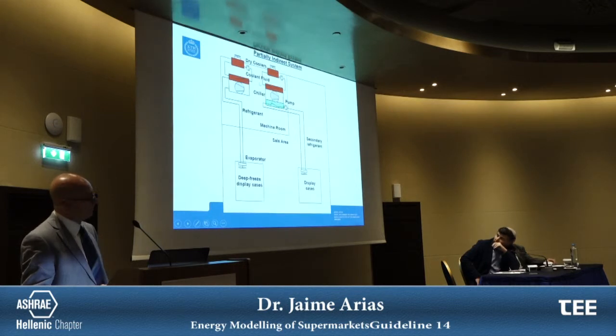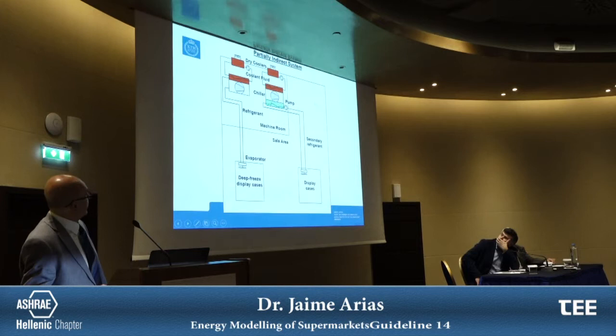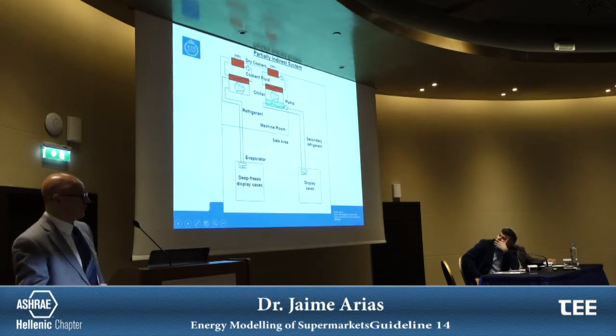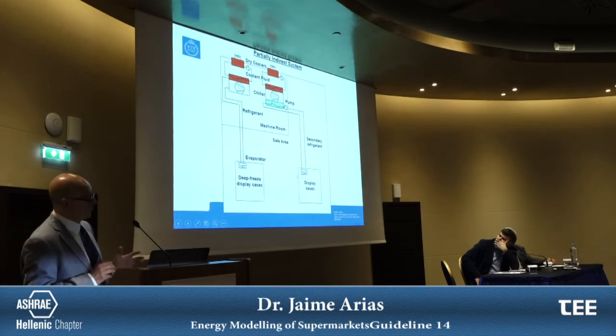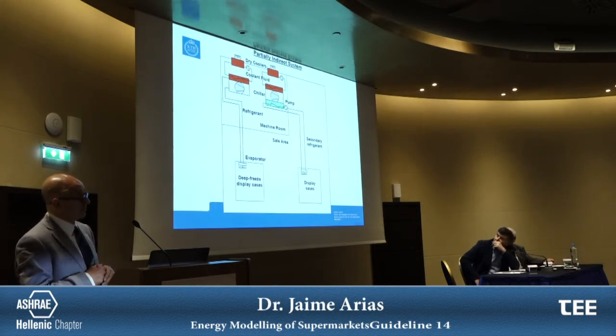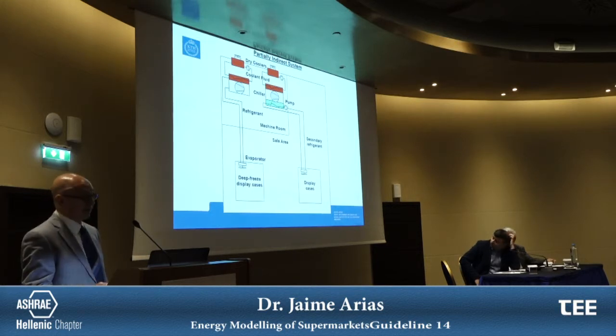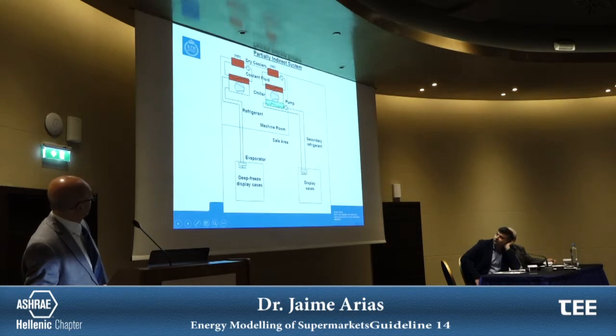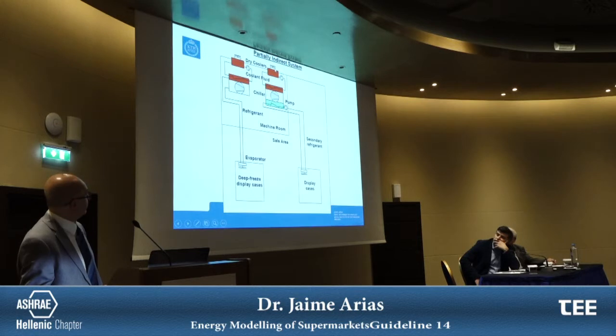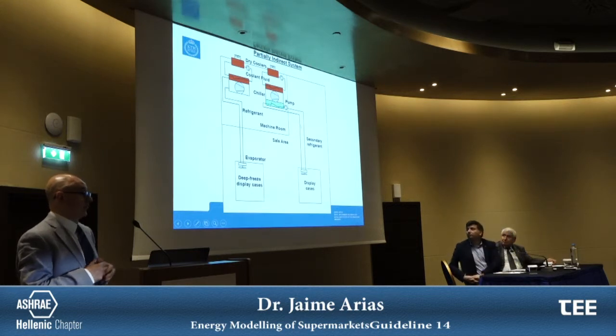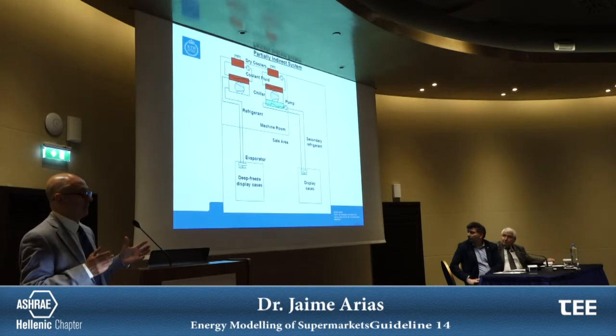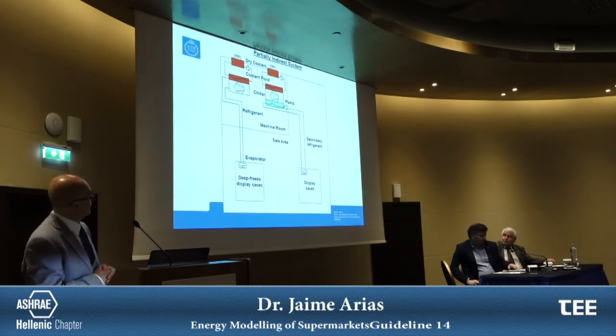And in Sweden, we installed this system, we call partial indirect system. So we have a chiller, we have a secondary refrigerant. In the majority of the cases, it's propylene glycol. The temperature of this secondary refrigerant is -4, -8. So the evaporation temperature for the medium temperature level is around -12. And we have another loop here. We call this coolant fluid, and we have a dry cooler on the roof. The main idea for this one was to reduce the refrigerant charge. So, for example, today it would probably be an idea, instead of having a chiller with R404A, to have propane, for example. So it's only to remove the chiller and put in a new one. It's one of the possibilities we are also looking at probably in the future.